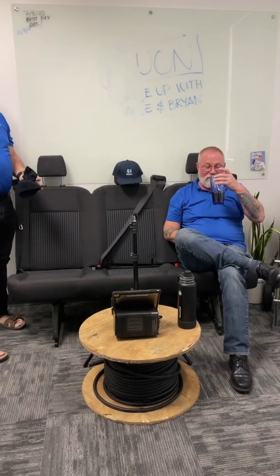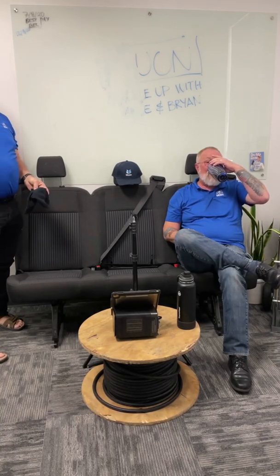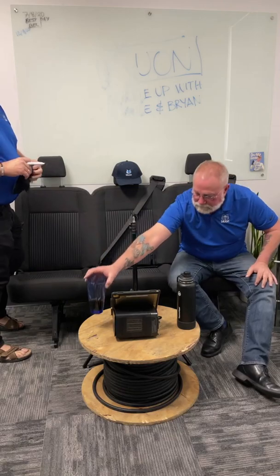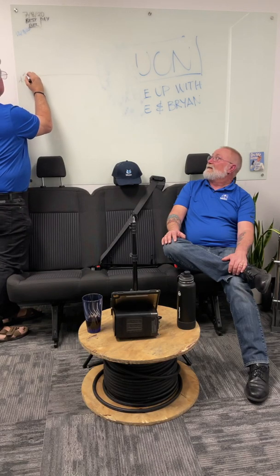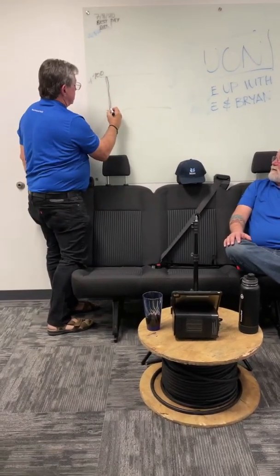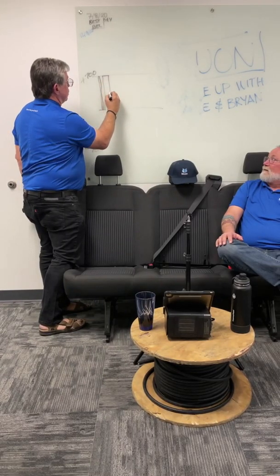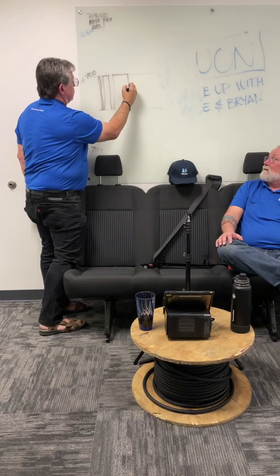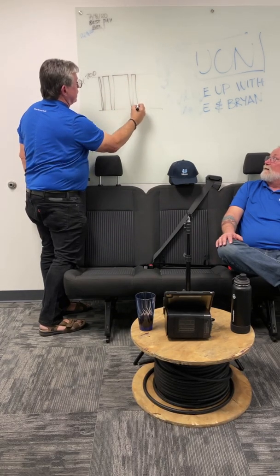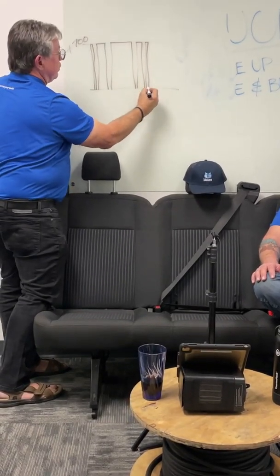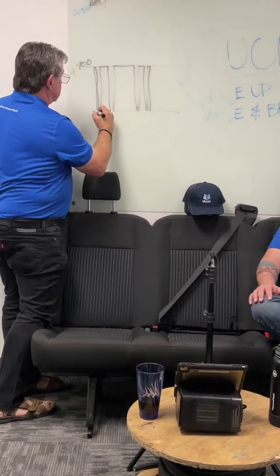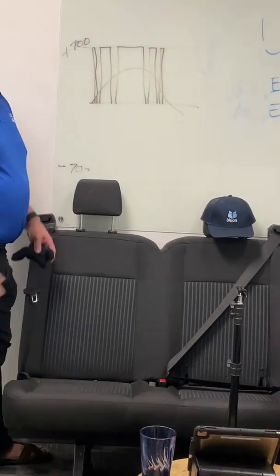So I'd hit you with the question: is the voltage going out to the motor on a variable speed drive AC or DC? What happens is, if I have plus 700 volts, zero, and minus 700 volts, the width of the pulse - if it's very quick, then the next one gets larger and stays on longer, and it continues to build, then works its way back down - and if you look at the average of these different points, what you have now starts to look like an AC sine wave going out to the motor.